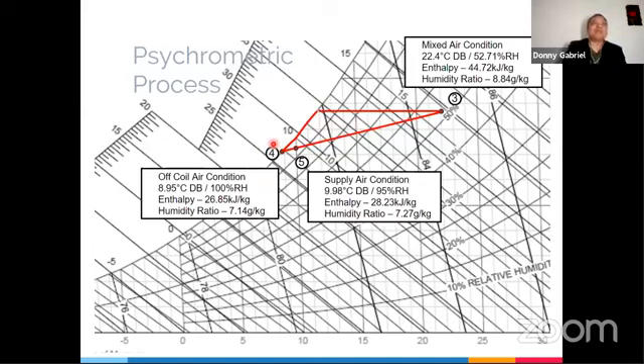Usually this bypass factor is very small. Sometimes it's 0.001 or 1%. So same principle as earlier. From this point to this point, this is your bypass factor. So for me, my bypass factor, I think this is about 5. If I'm not mistaken, it is about 5%. So this 5% now here is the representation of the bypass factor. This small line here is 5% of this bigger line.